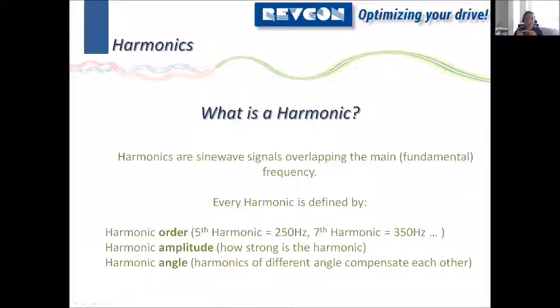Then we have the harmonic amplitude. That is, how strong is this signal? How strong is the amplitude of this frequency? So looking at the fifth harmonic, how strong is the amplitude of the 250 hertz signal? This can typically be voltage or current. A harmonic is not specifically meant for current or voltage. It's made for both. And in some different topics, for example in audio, it can have a completely different sense.